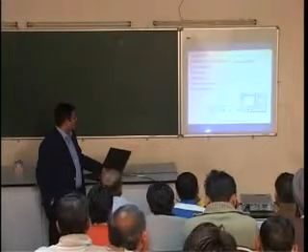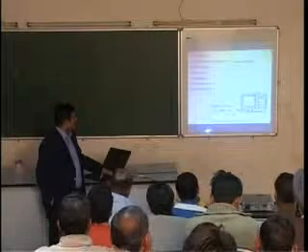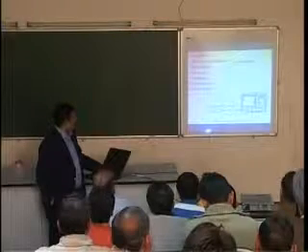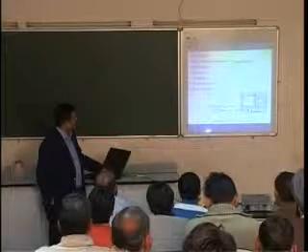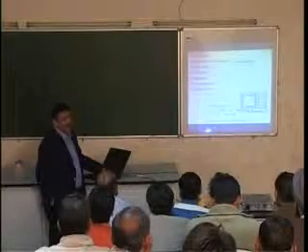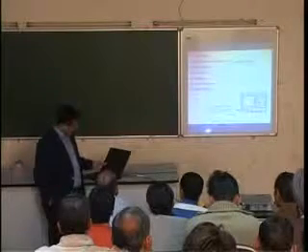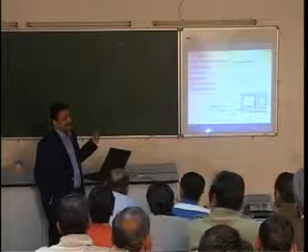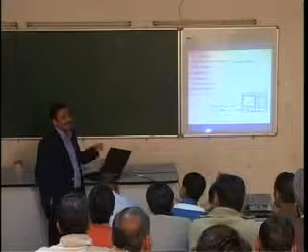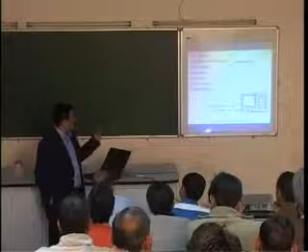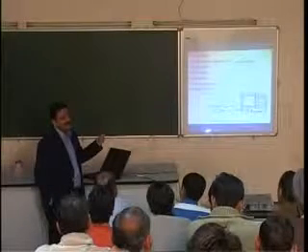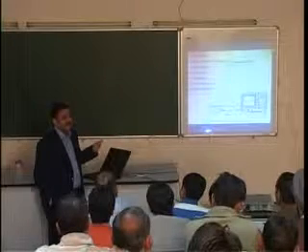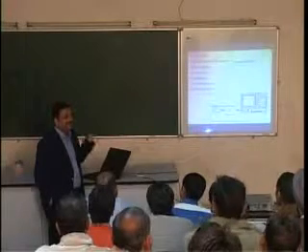But other errors, for example, there can be nearby fluorescent lights or nearby instruments and computers. We have even seen that the Wi-Fi system which people are using also affects. Suppose you are doing a development in the same band, generally these are at S band, and you are doing the measurement many times. Once we had this problem and we spent nearly 1 week to identify it. It used to be an intermittent problem.